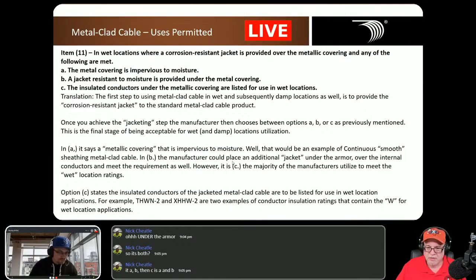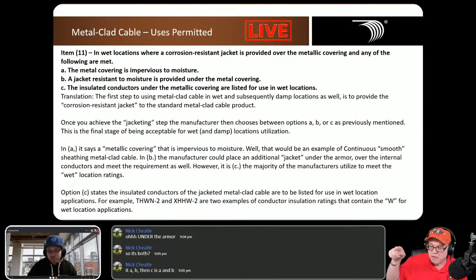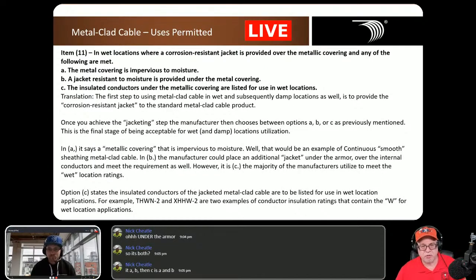And of course, third is the C, which is what we all do, and we put wet location rated conductors in there. So even if it's rated for use without the PVC on it, and we use it indoors like normal MC, the conductors inside of it are still going to be wet rated. Whether or not it's a dry location only product, it can't become wet rated unless it meets the general requirement and one of the options A, B, or C. And we use C. Most all manufacturers will use C. And again, that's where you see THWN-2 and XHHW-2, which is typically what is used in those products.